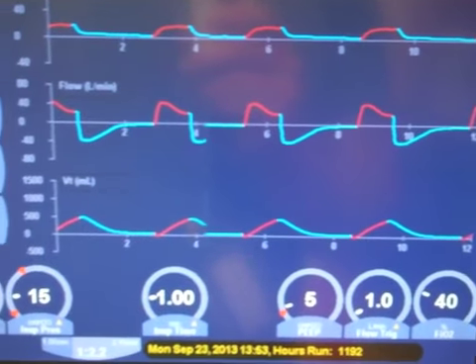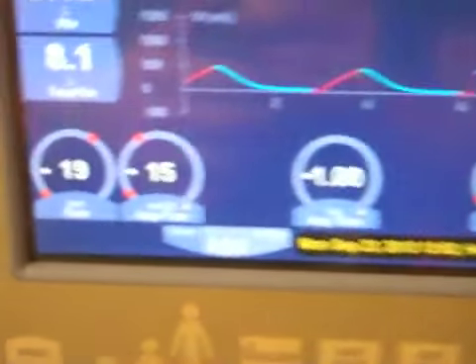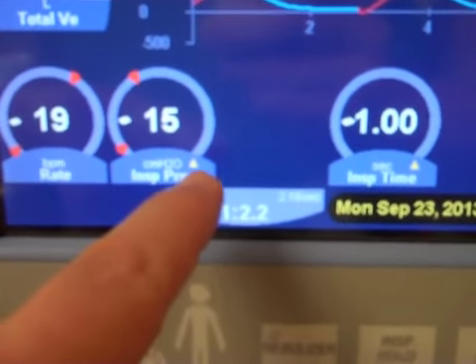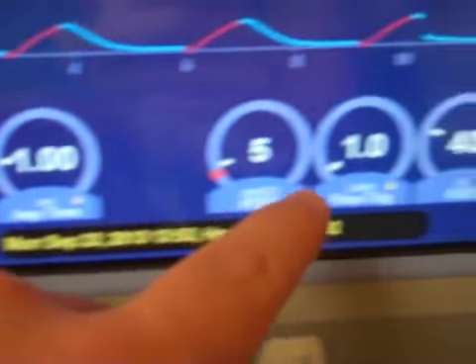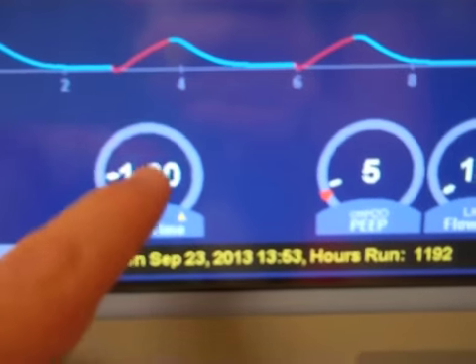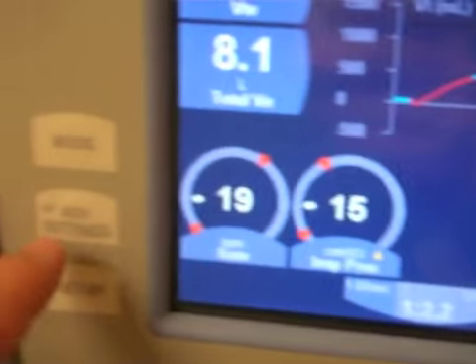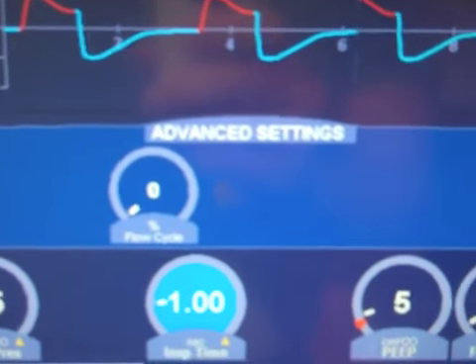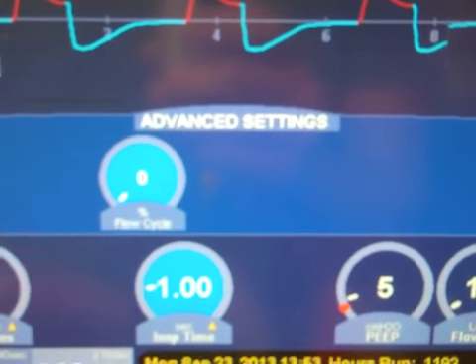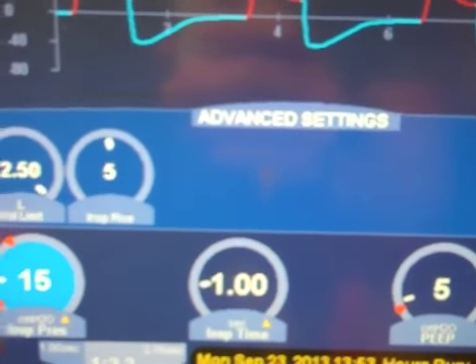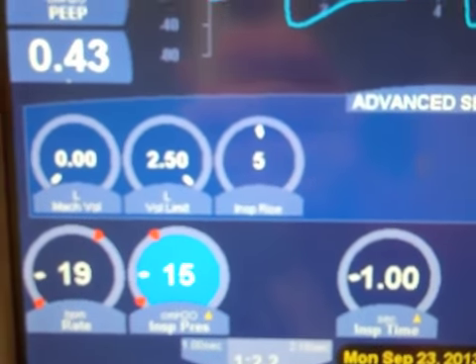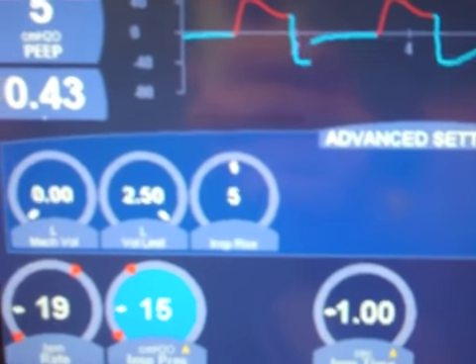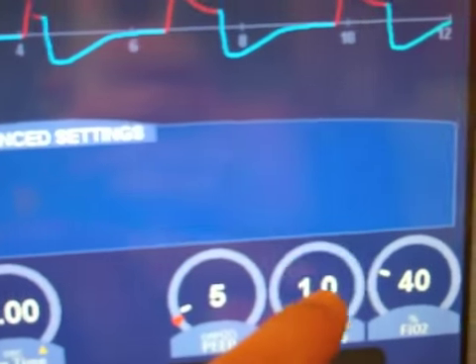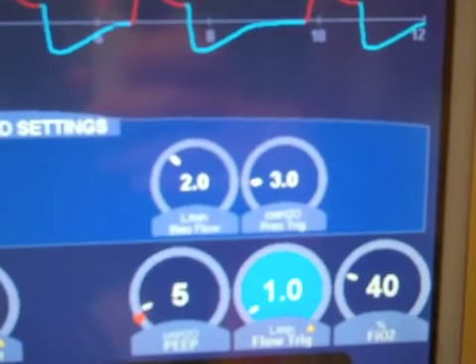Other things that are really neat about this ventilator, it's got some advanced settings. So some of these modes or parameters, down at the bottom you'll see this yellow triangle. Anywhere you see that yellow triangle, you can touch it, hit advanced settings, and there will be things in the back that you can actually set. So you can set a flow cycle instead of time cycle. If I set my inspiratory pressure, I can look at volume limiting those breaths. Or I could even go in and set a pressure trigger.